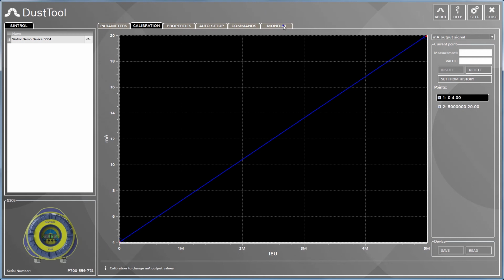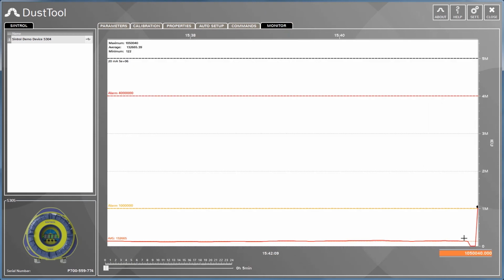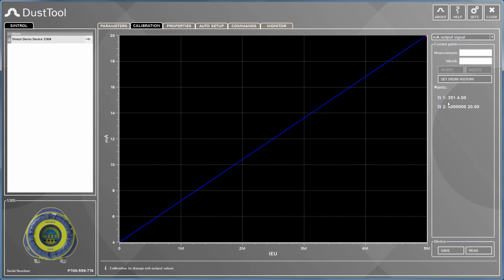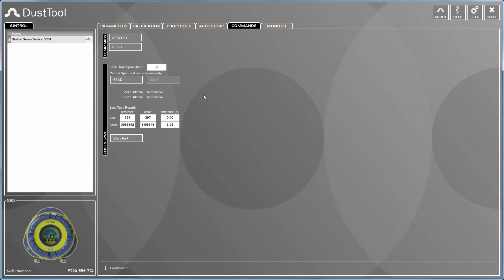What happens now? If we go to the monitor view, it first checks the zero level, then it checks the span level, then it goes back into measurement mode. And if we go back to the calibration, we see that not 0 IEU but 351 IEU have been set to be the 0 level. This is close to nothing, close to no change, but however, in future, the 0 and span check is referenced against that value.